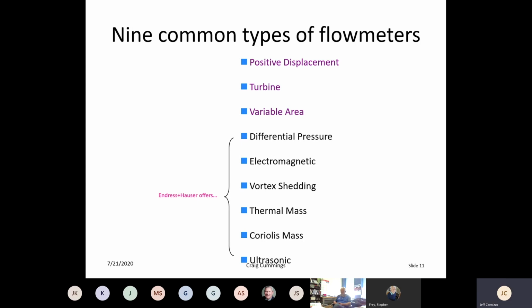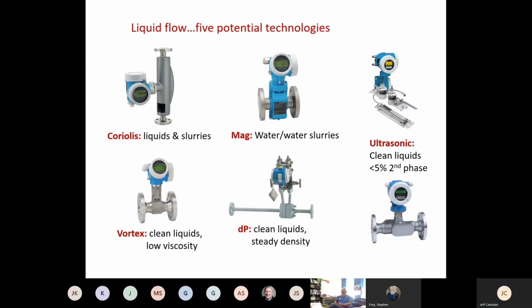So of the flow meter types that are out there, there's probably 9 common types. There's always some offshoots, but there's 9 common types. Endress+Hauser actually offers 6 of these types: differential pressure, magnetic flow meters, vortex shedding meters, thermal mass, Coriolis mass meters, and ultrasonic meters. So in liquid flow, we offer 5 potential technologies: Coriolis, mag meters. Ultrasonics are limited to clean liquids. Typically, we manufacture a transit time ultrasonic meter. Vortex shedding meters, DP meters.